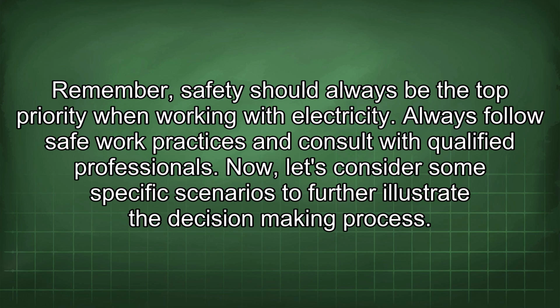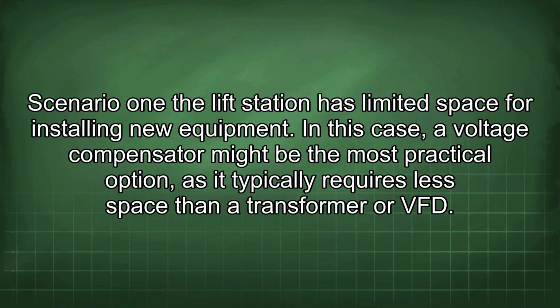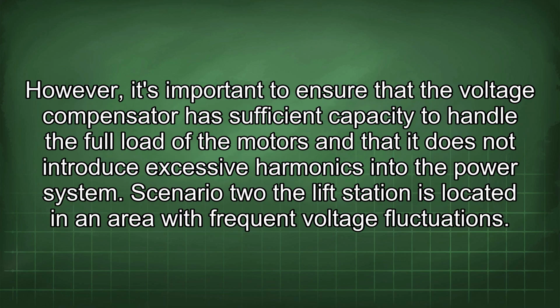Now, let's consider some specific scenarios to further illustrate the decision-making process. Scenario 1: the lift station has limited space for installing new equipment. In this case, a voltage compensator might be the most practical option, as it typically requires less space than a transformer or VFD. However, it's important to ensure that the voltage compensator has sufficient capacity to handle the full load of the motors and that it does not introduce excessive harmonics into the power system.